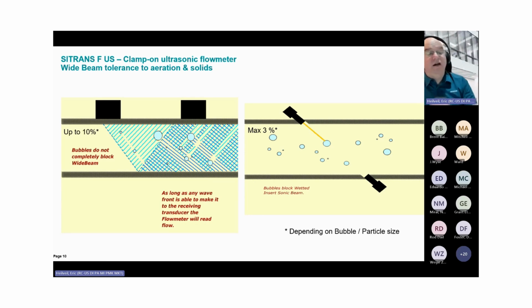Now, I've gone ahead and said that, I would like to mention that it is possible under some situations, under extremely challenging conditions, where we can mount these transducers clamp-on style in a direct mode. The reason you would do that is that if you had an extremely challenging flow with a lot of turbulence or a lot of interruptions, and you just had to shoot direct, you can do that. We would prefer to do it the other way because we can get a lot more information and be a lot more accurate over a wider range of conditions, but you can mount direct if so required.